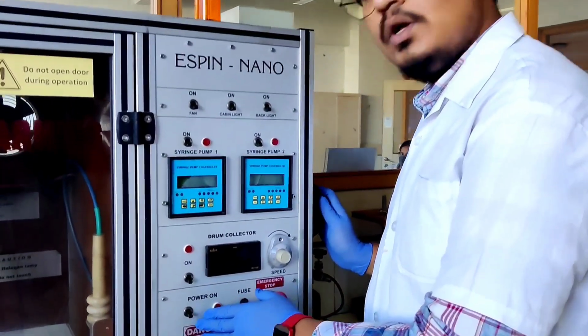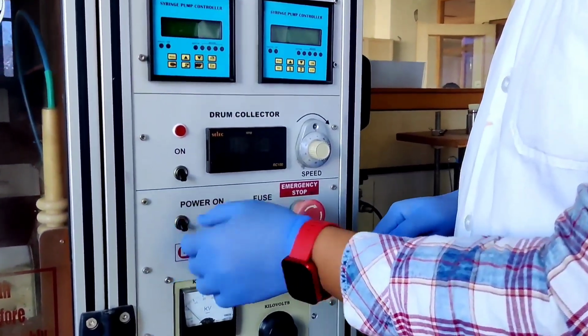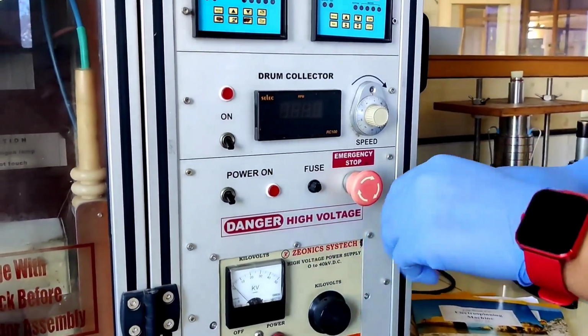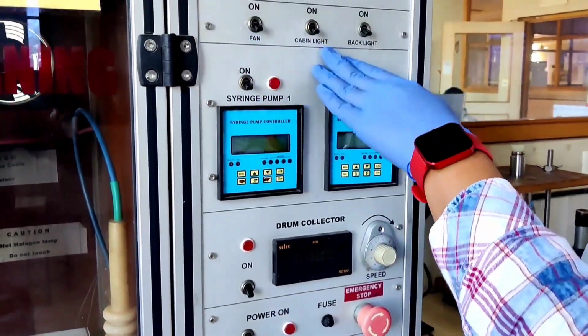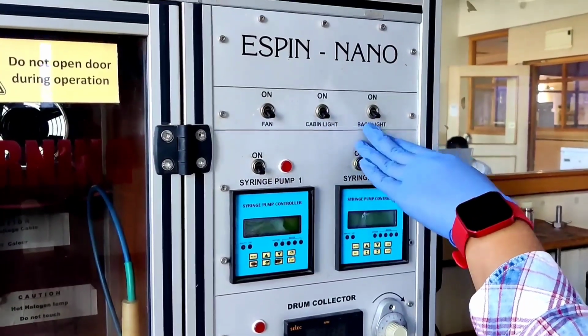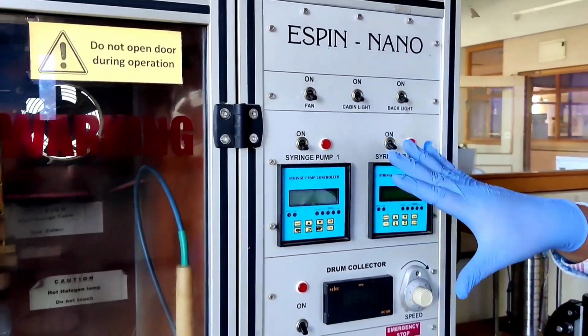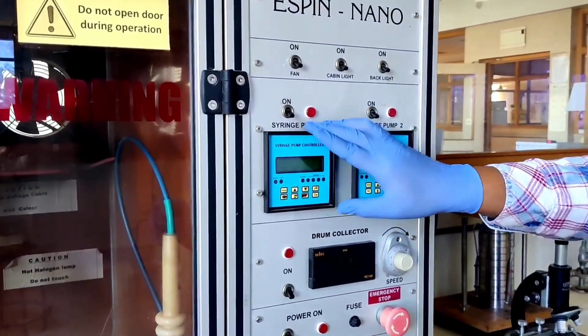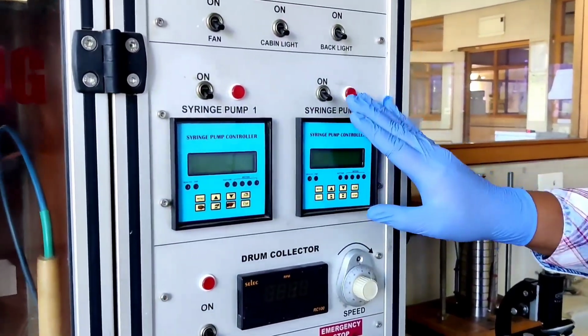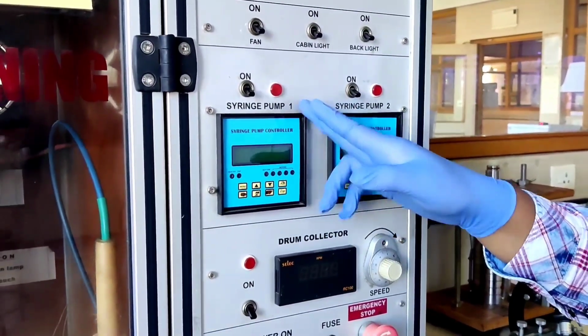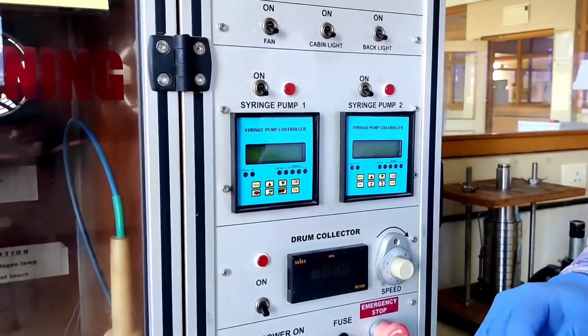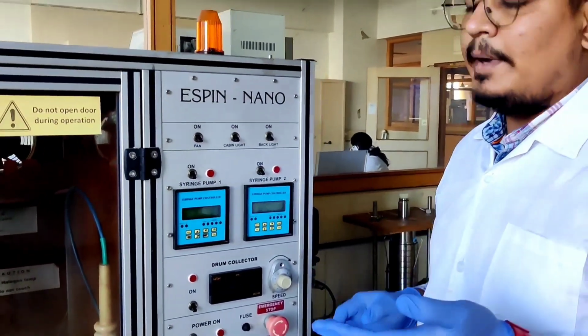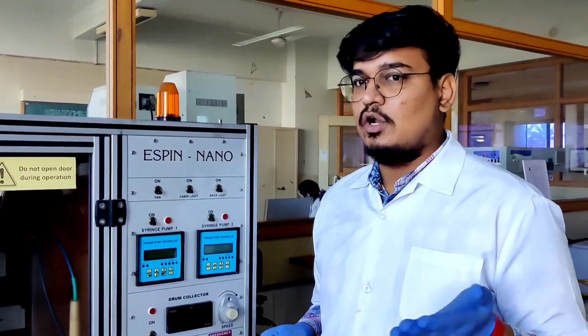Here is the main switch which is used to turn the main system on and off. Then here are the switches for the fan, cabinet light and the backlight. Then the syringe pump, which controls the flow rate of the system. This flow rate is usually 0.2 to 0.4. It all depends upon the nature of the polymers, whether it is natural or synthetic.